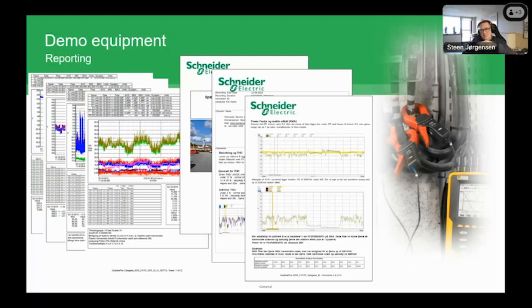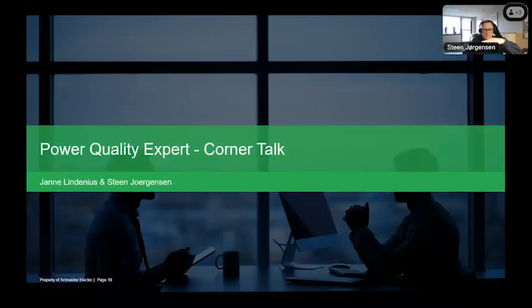That means that, let's say the CTs are measuring a level of 30% harmonic current, and you have a set point that says 5, it will actually try to put in harmonic current, but 180 degrees opposite, so it's working like a noise cancelling system. But if the CTs are put in the wrong place, you can actually pollute the system even more than you're actually measuring. So it's very important to have the CTs connected correctly, and if they're connected correctly, you only need 1 breaker. So it's quite easy to install this.